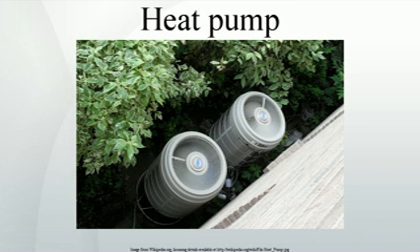This is a standard refrigeration cycle, save that the cold side of the refrigerator, the evaporator coil, is positioned so it is outdoors where the environment is colder. In cooling mode the cycle is similar, but the outdoor coil is now the condenser and the indoor coil, which reaches a lower temperature, is the evaporator. This is the familiar mode in which air conditioners operate.